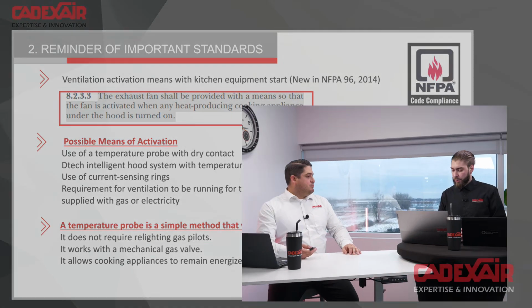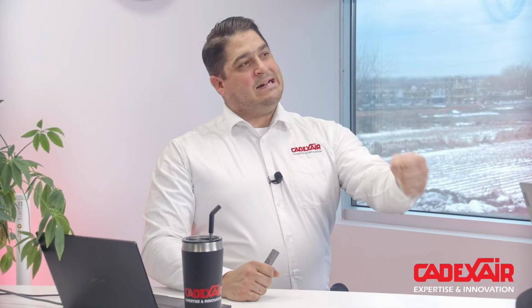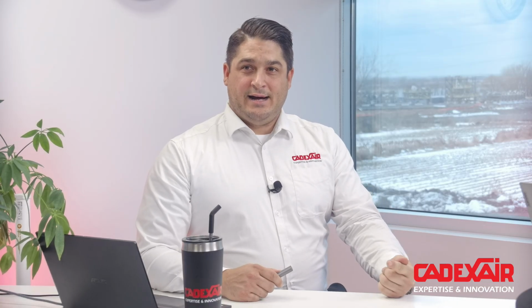Yes, Mike? I have a question from another participant. Is makeup air required for all commercial kitchen ventilation systems? That's a good question. In fact, they will not say that a makeup air is required. In the code, and I don't know the exact value, but somewhere I think in chapter 8, called air movement, they say that you have a maximum differential of pressure that you can have inside of a restaurant. And there's a specific value, I don't remember it off the top of my head. But probably everybody has gone to a restaurant, tried to open the front door, and it's really difficult to open. That's a case where there is no makeup air, or the makeup air is not running.